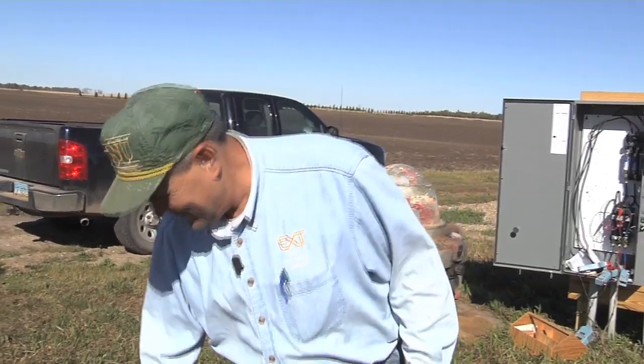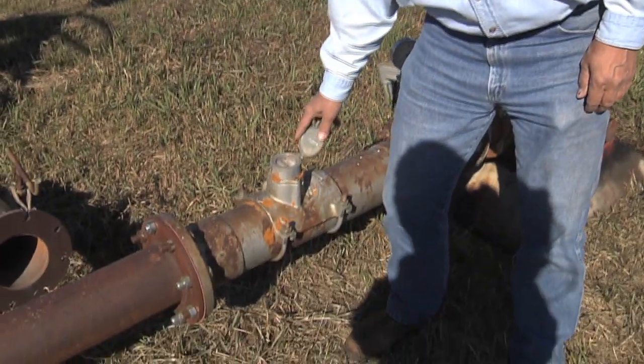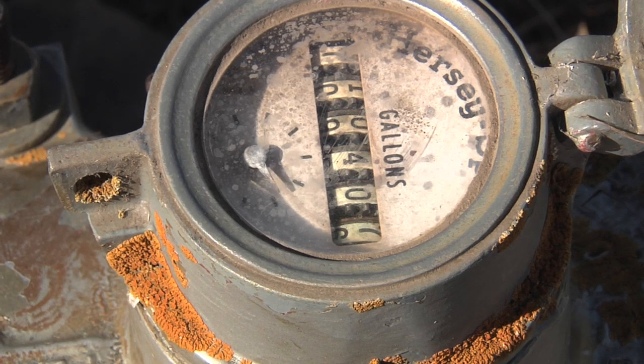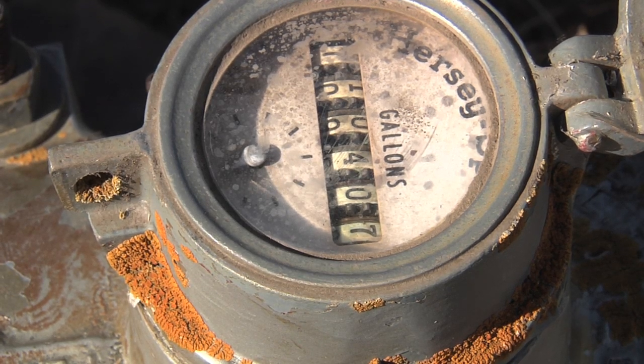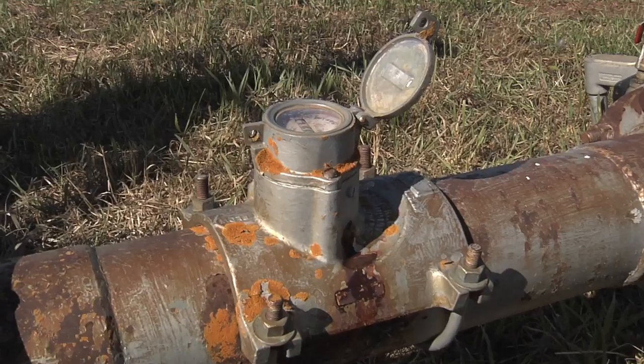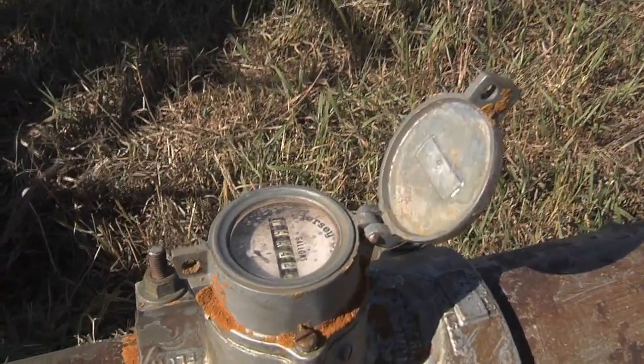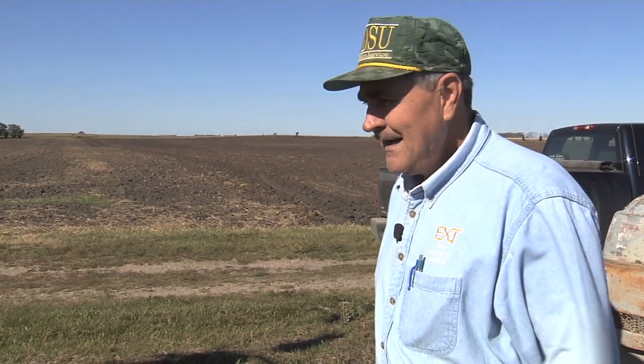This is a common sight here on most irrigation systems. You have a standard propeller type meter, but here in the northern plains, after a few years, these have a propeller inside in the pipe, and the freeze-thaw cycle seems to wear out the bearings, and quite often they don't work. So for a pump test, I need an accurate measurement of the flow rate so that I can get an idea of how much actual power is in the water. So we're going to use an ultrasonic flow meter, and I'm going to clamp on the pipe right down here. I have a nice long, as straight a stretch of pipe as I can get, so I have uniform flow, and then I'll get a more accurate reading.